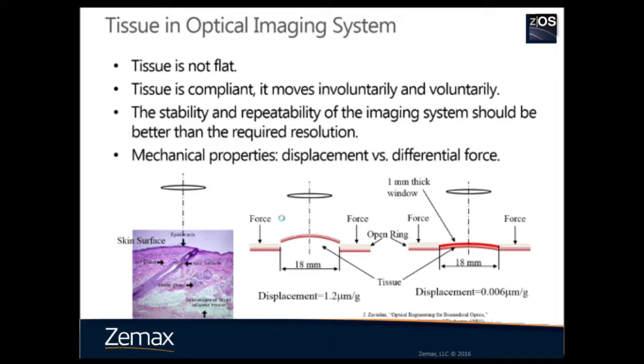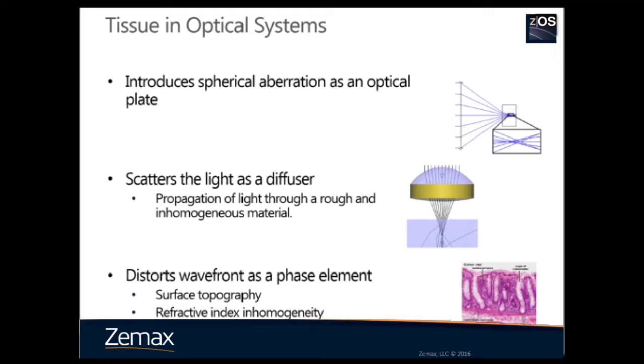The tissue is part of the optical system, so we need to understand its impact on system performance. Even if you design a perfect system, when you scan into the tissue, the tissue will introduce spherical aberration, just like an optical plate. The tissue also scatters light like a diffuser, so even with a great system, the spot size is much larger due to scattering. The tissue also distorts the wavefront due to surface topography and refractive index inhomogeneity, decreasing system performance.